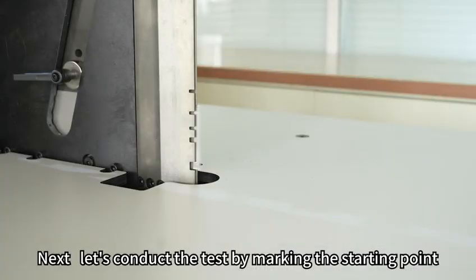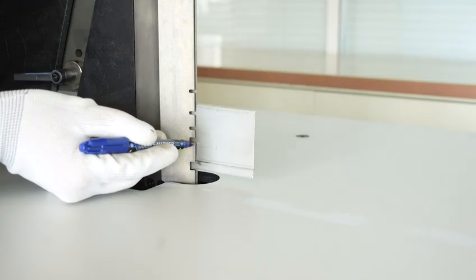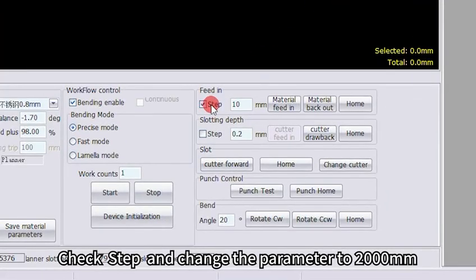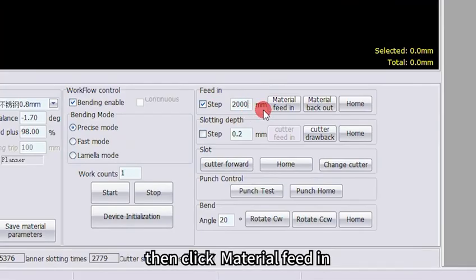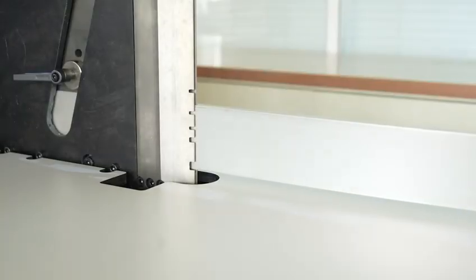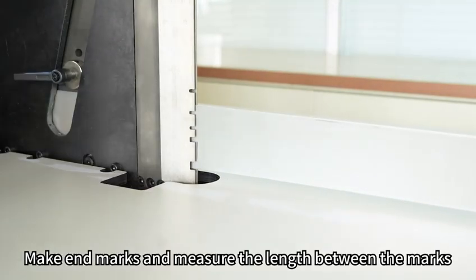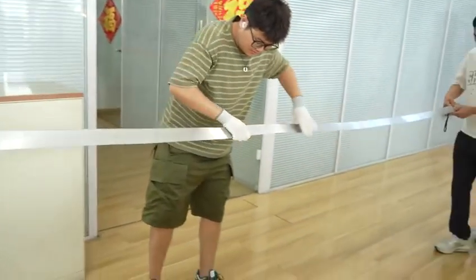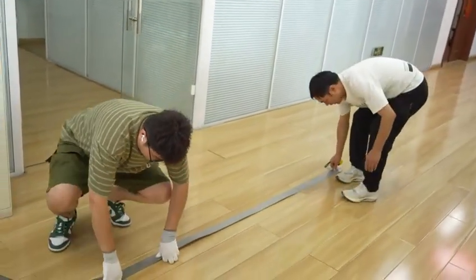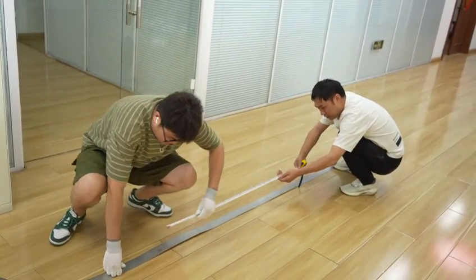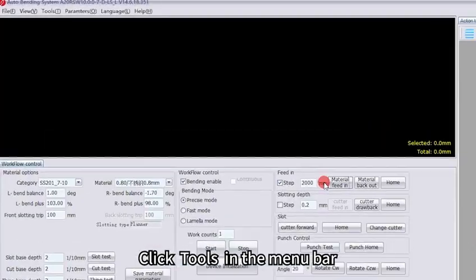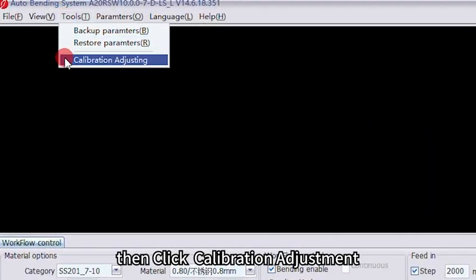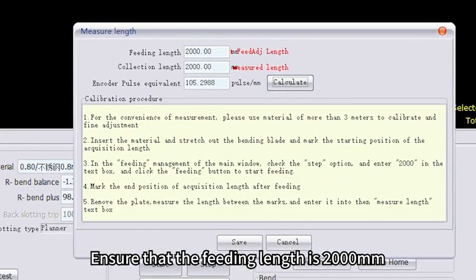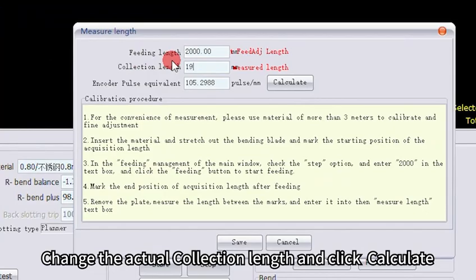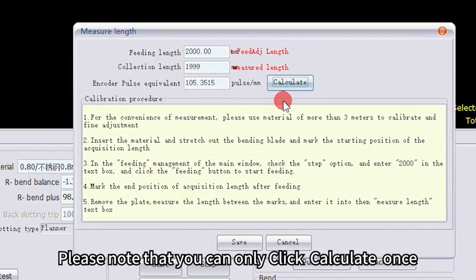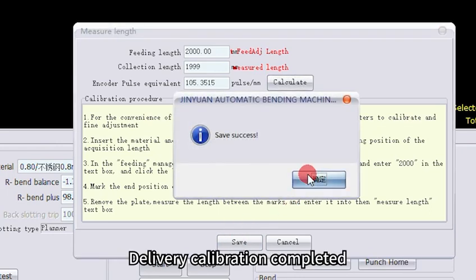Next, let's conduct the test by marking the starting point. Check step and change the parameter to 2000 mm, then click Material Feed In. Make end marks and measure the length between the marks. Click Tools in the menu bar, then click Calibration Adjustment. Ensure that the feeding length is 2000 mm. Change the actual collected length and click Calculate. Please note that you can only click Calculate once. Click Save. Feed calibration completed.